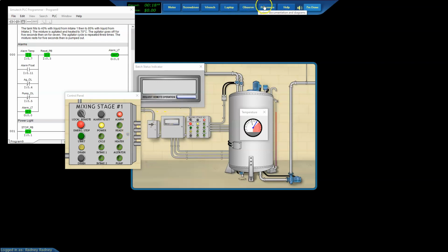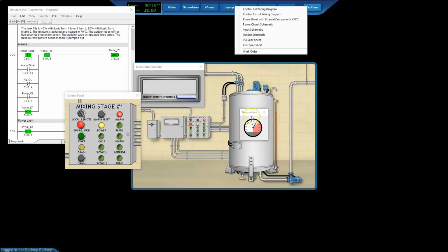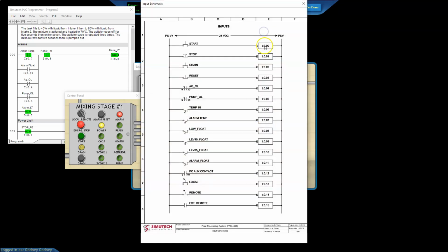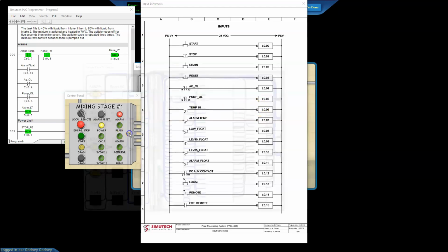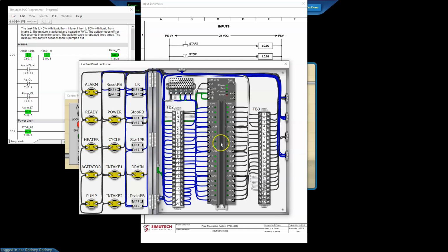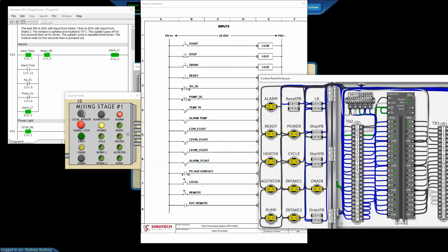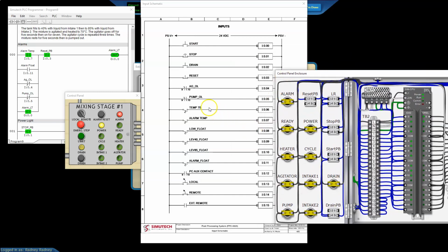And we can go to our reference and look at I/O. We have to be somewhat in a hurry because we do cool down. But let's just see where our alarm temp is, it's bit 7. Now bit 6 should be on because we definitely reached 70 degrees, but the problem is we went over it. Aha! Bit 7 is on, showing us we went over it, but bit 6 is not on. So something has to close when the temperature reaches at least 70, and we went even higher. That seems like a problem. Why would we show a temperature above 70 degrees, but not show a temperature of 70 degrees?